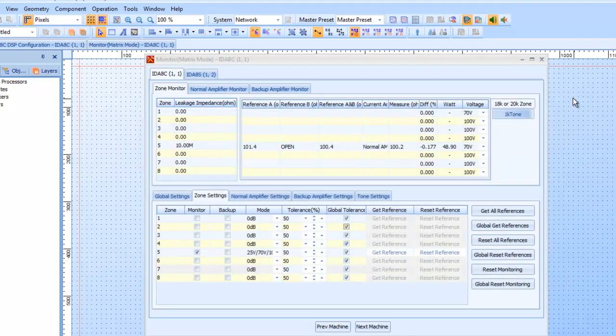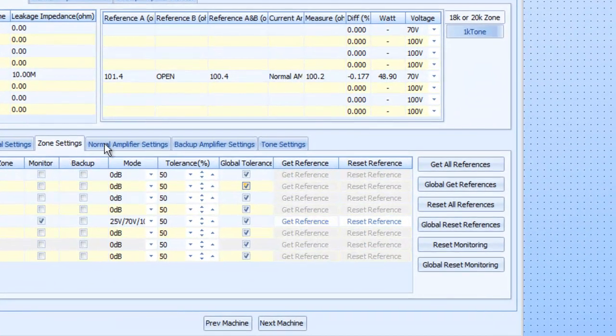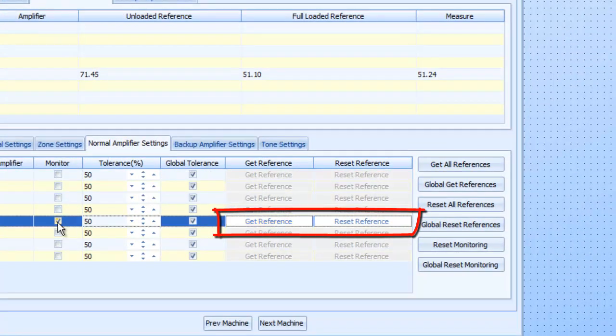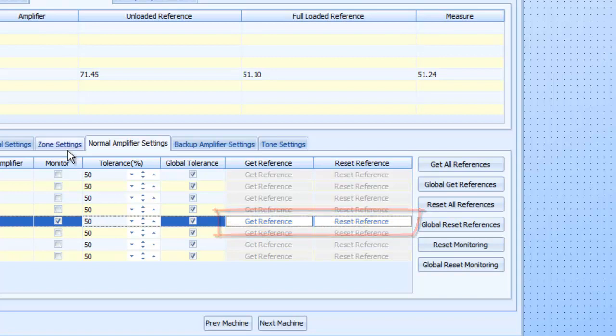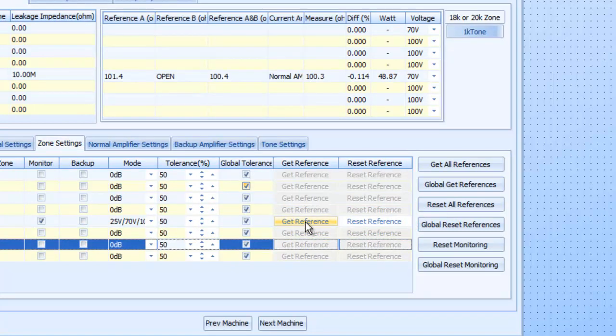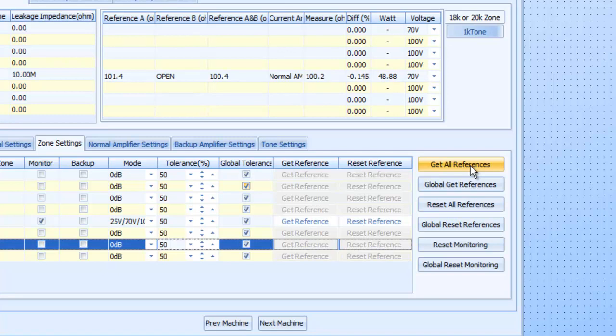Now I can close it. Now you notice when I'm in either one of these, the only one I have enabled for backup or monitoring actually has get reference and reset reference tabs open. If we go to the zone settings, same thing. There's my zone five and there's a get reference. You could say get all references and it would go through every single amplifier and every single speaker circuit. And if you're near the unit, you will hear all the relays clicking in and out as it switches between one output and one amplifier circuit and another.